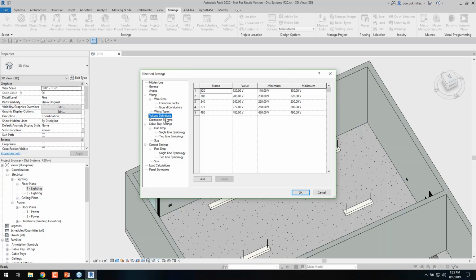And then with those voltages, what you can do is build distribution systems. So you can say, all right, I want a 120/208 system that's a 3-phase Y configuration. The line to line is 208 and the line to ground is 120. And so you could start to create any unique types of distribution systems that you need.